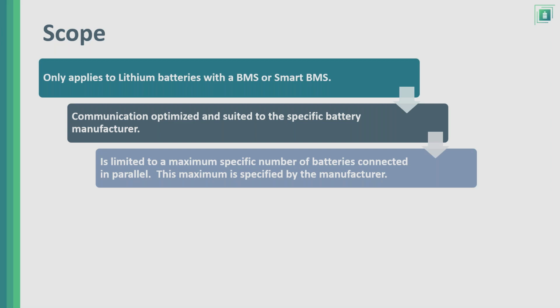Remember, we're talking about communicating batteries among each other, not necessarily connecting batteries in terms of power into the system. We could have more if we want, but to communicate them, with EVO Maxes you can have 20, and with E-Flexes, we can have 30 batteries communicating between each other, and then from the first battery communicate to the inverter.